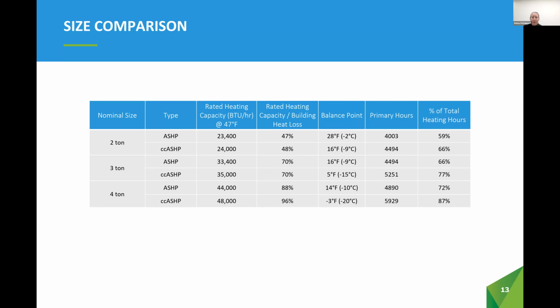While you could size a heat pump to meet all of the heating season hours, there are disadvantages in doing so. This will result in a higher upfront unit cost, poor unit performance from short cycling and reduced overall efficiency, reduced equipment lifespan, thermal stratification resulting in hot and cold spots, poor dehumidification performance, and acoustic implications. No matter how your heat pump is sized, an auxiliary heating source will be required for use in our cooler climate.